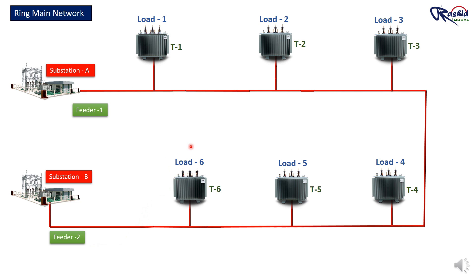But even this system is not perfect. The problem here is that there are no switches. If Feeder 1 has a problem, we can't disconnect the fault area because there are no switches to control it. Also, the transformer, which is very important and expensive, doesn't have any protection. So how do we make this system better?